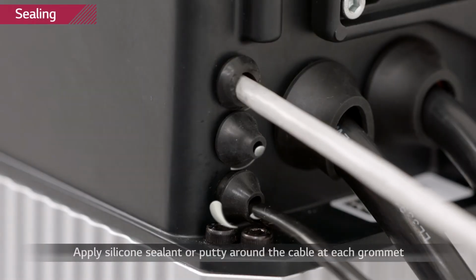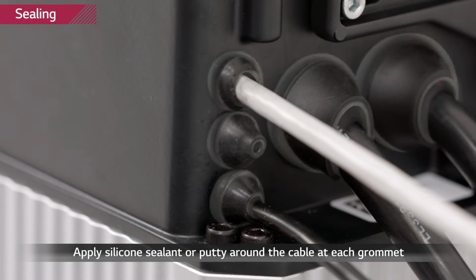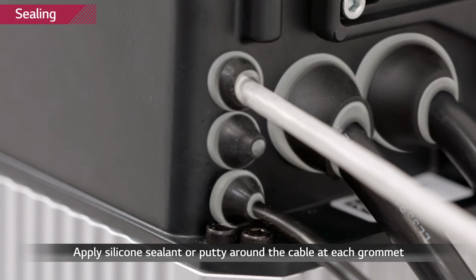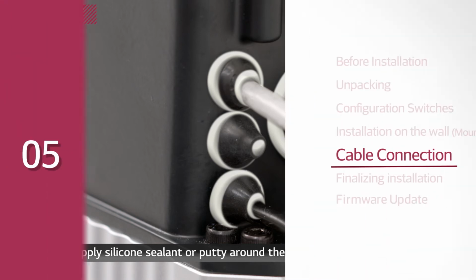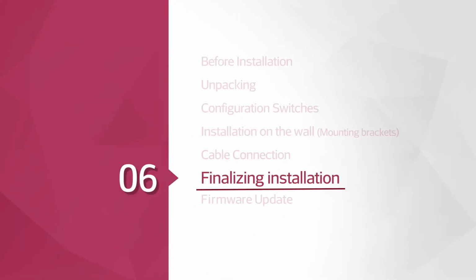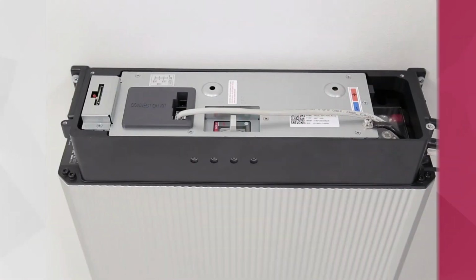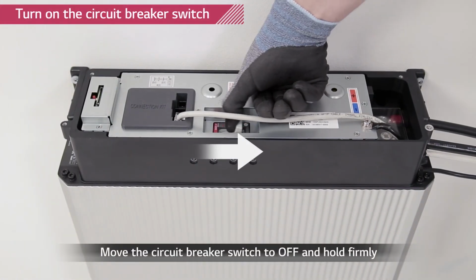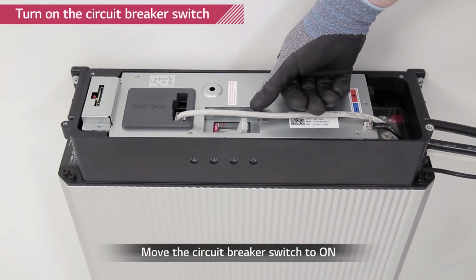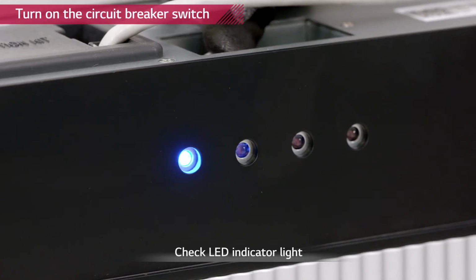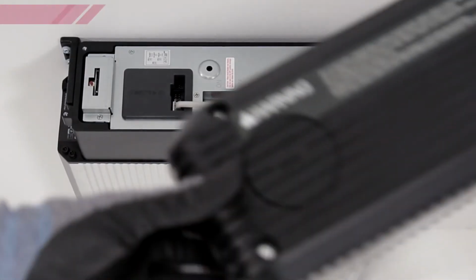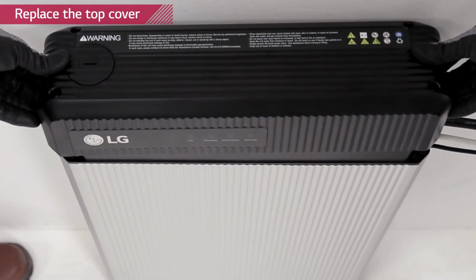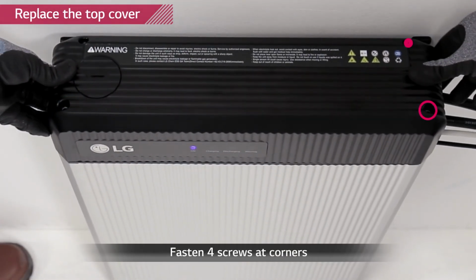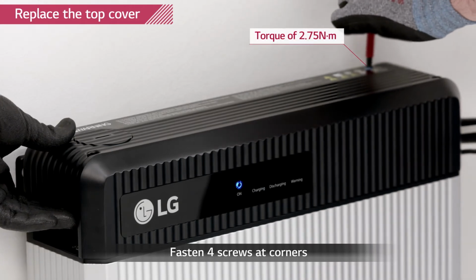Use the small grommet to cover up the middle hole. Apply insulating sealant to all the areas where the grommet meets the cable and the hole. Turn on the circuit breaker by switching it to off position first, and then to on position. Close the top cover and tighten the 4 hex socket screws with a torque of 2.75 Newton meters.